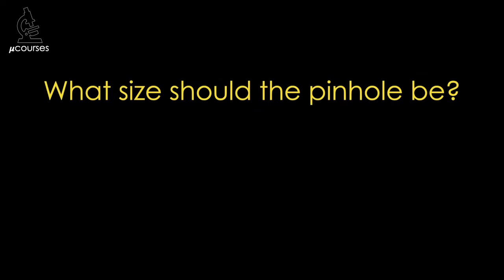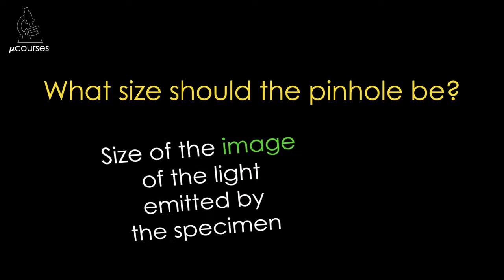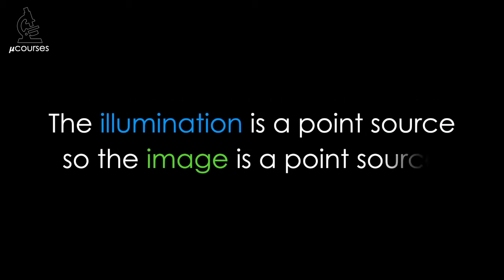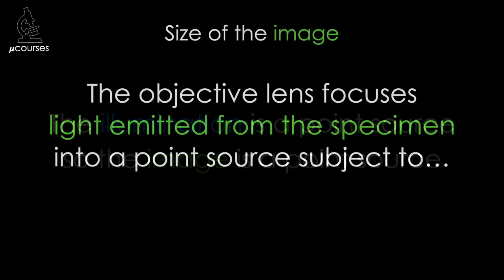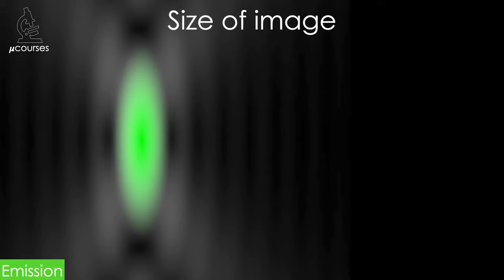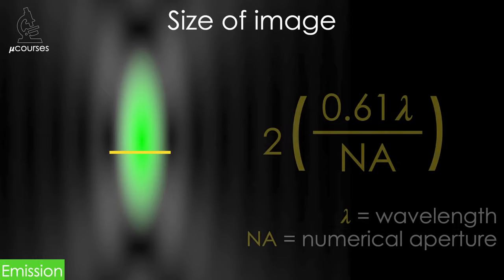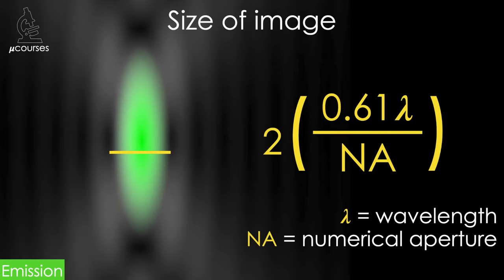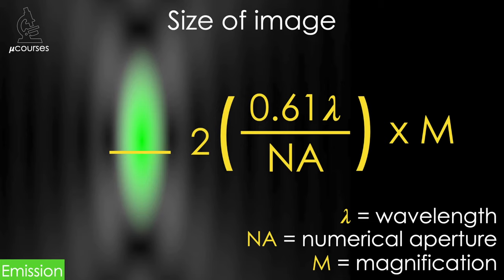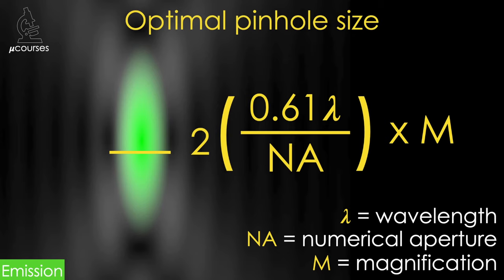If blocking out-of-focus fluorescence is the priority, the pinhole should be adjusted to match the size of the image that reaches it. Illumination of the sample with a point source leads to an image of a point source of fluorescence, and when we image a point source with an objective lens, the image is subject to the point spread function. We can therefore calculate the size of the image using the equation for the diameter of the point spread function, and since the image is magnified, we multiply by the magnification. This equation gives us the physical size of the pinhole needed to maximize reduction of out-of-focus fluorescence. In confocal software, this number is usually referred to as one Airy unit, or one AU.